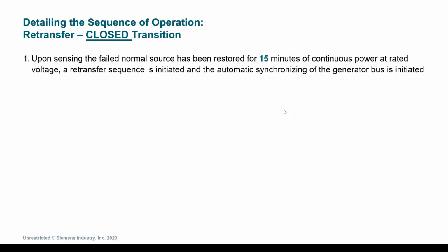Now that we know how the equipment operates at a utility or normal source loss, we want to look at how the equipment is retransferred. And we want to start with a closed transition example. So quickly, a closed transition means that when the equipment goes from emergency source to normal source, there is no interruption in power. This is something that's very important to coordinate, not just with the facility, but also with the utility company and any end user in terms of operational impacts. It's also important that the transfer switches that are existing are identified and reviewed, that their functionality is built into this. And we'll touch on that in a second.